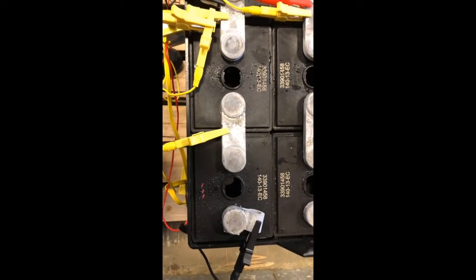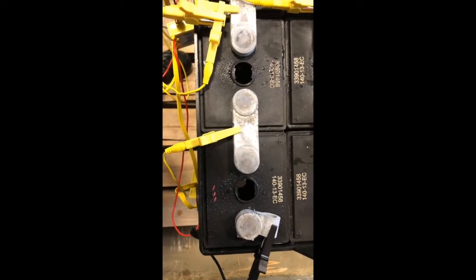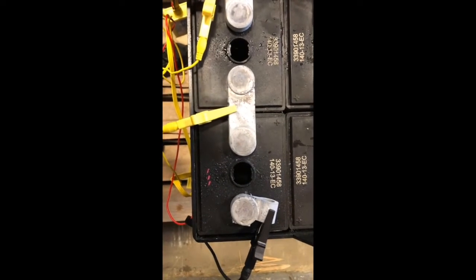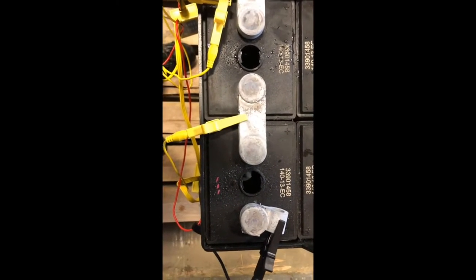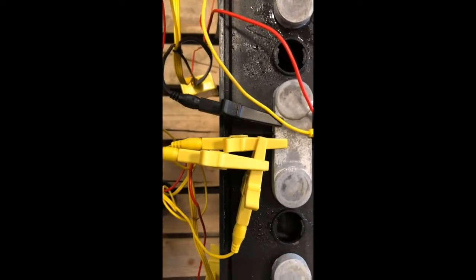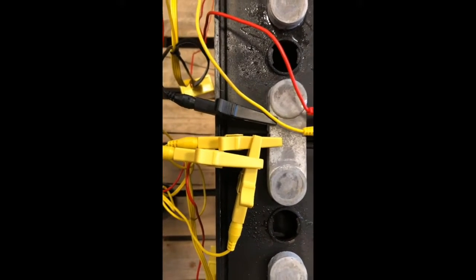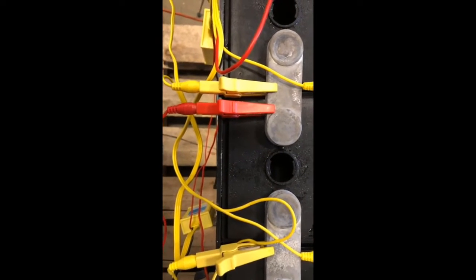When we get to the end of a module and an uneven number of battery cells divided by 4, we have to distort the wiring so that the negative is our reference point on the main negative of the battery. The shortest yellow is on the positive of cell number 18. The other 3 yellows are stacked with the negative on number 17 positive, and the red lead has to extend out 2 more cells to number 15 positive to give us the 8 volts necessary to power up the module.